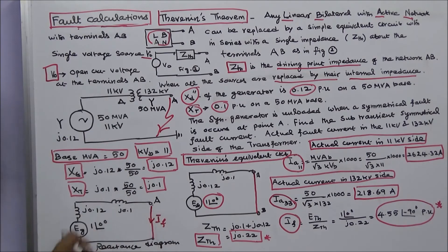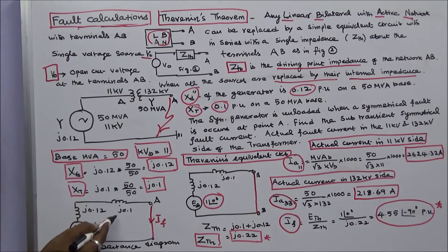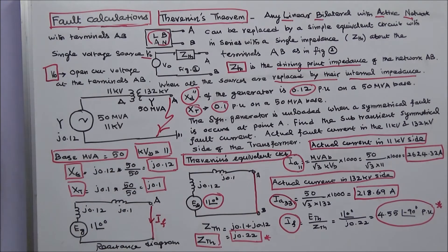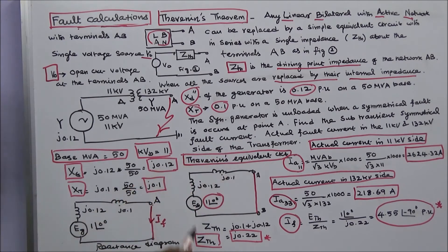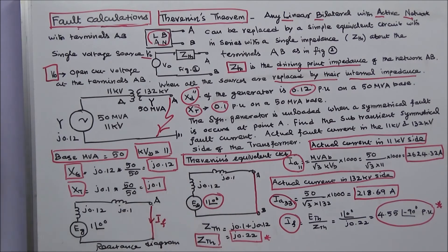Now I draw the reactance diagram. The voltage of the generator is 1∠0°. The reactance of the generator is j0.12 and the reactance of the transformer is j0.1. Next, I draw the Thévenin equivalent circuit. Here the Thévenin voltage is 1∠0°. Thévenin impedance is j0.1 plus j0.12, that is equal to j0.22. Now I can easily calculate the fault current.